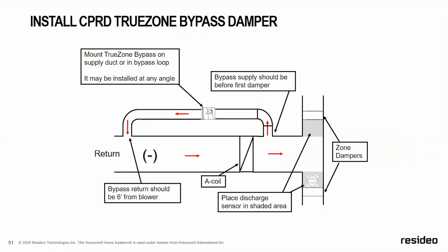This is typically where we install a bypass. A lot of our rules are there for protection. Typically 6 feet from a blower motor just means that if you're in a heat mode and your bypass is open, you don't want to overheat your motor. And again, the discharge air temperature sensor, they are in a shaded area. This is in our installation manual. I personally, in my market, do not recommend it. However, again, I would caution you to always call your contractor development specialist to help you with your zoning design. We're there to help.